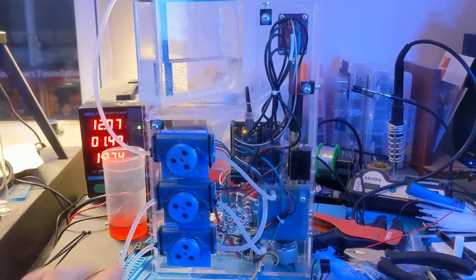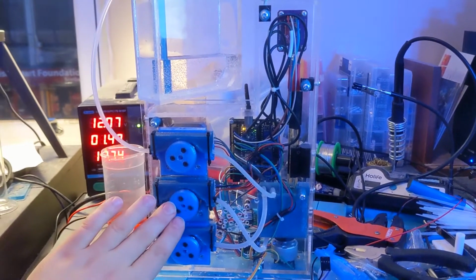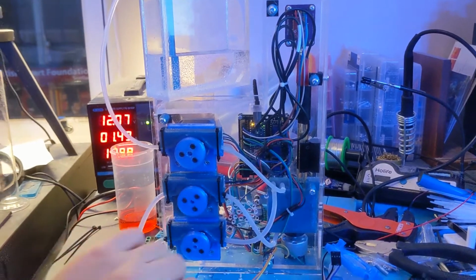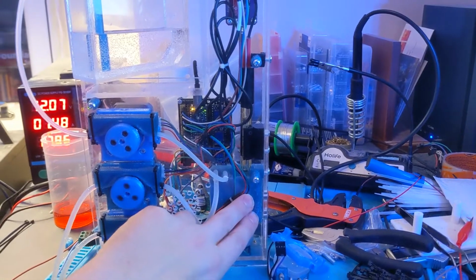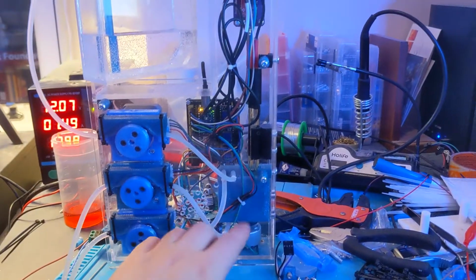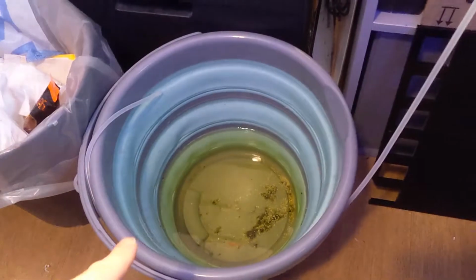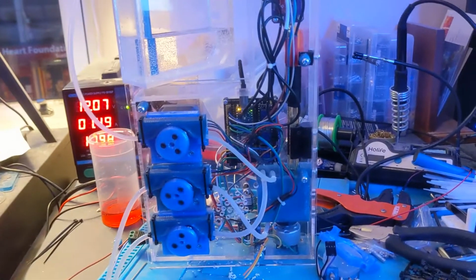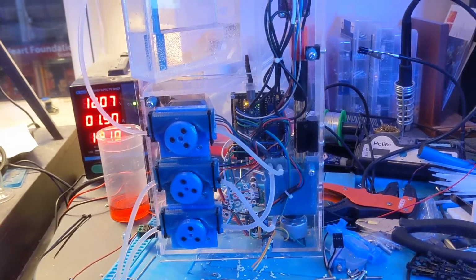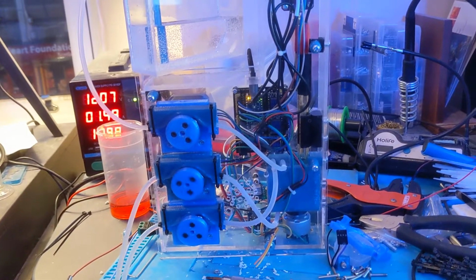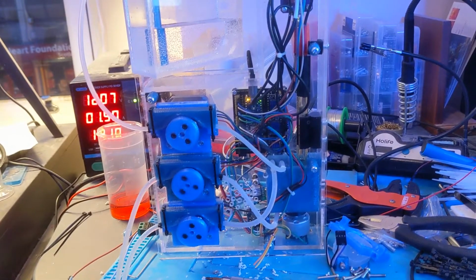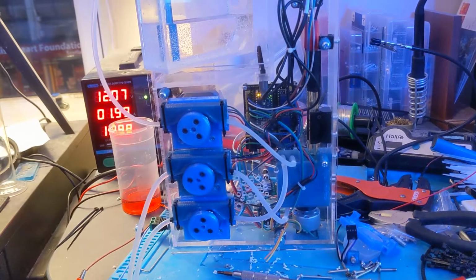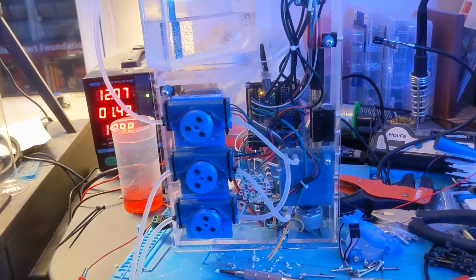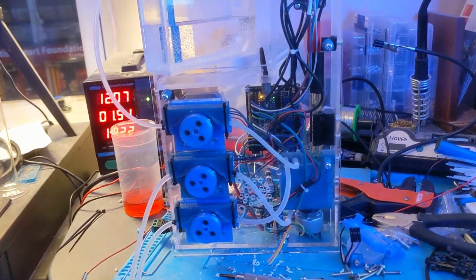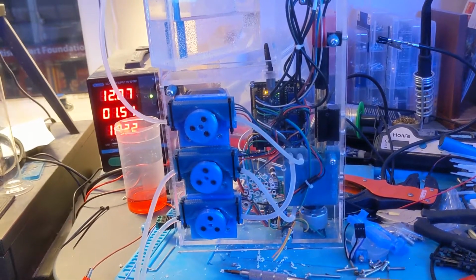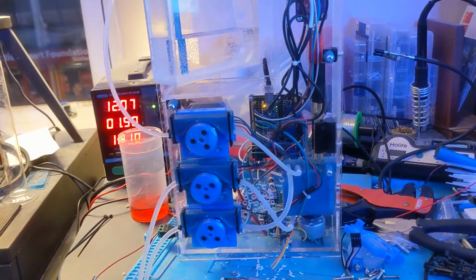As you can see, the middle pump here, which is the wastewater pump, has started running. What that's doing is clearing out this reaction chamber, emptying it into this bucket down here. It's going to run long enough that it can be totally confident that chamber is empty. It's going to run long enough to empty 50 milliliters out of there, which is the full volume of that chamber, although it's programmed to only ever load it up to 30 milliliters.